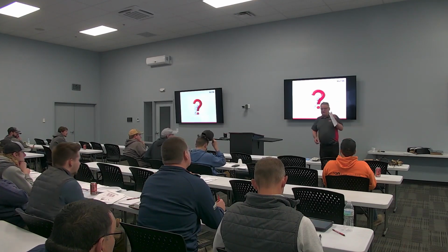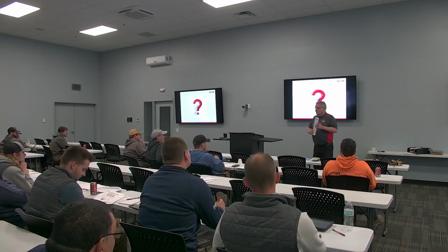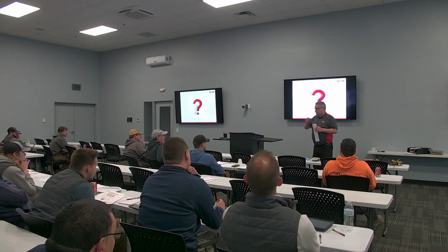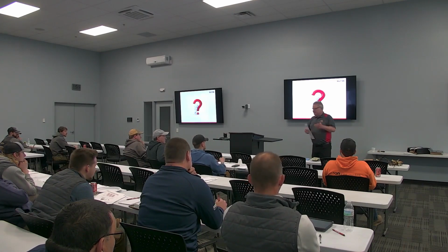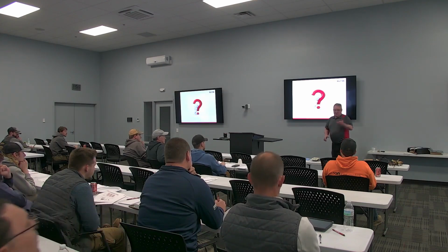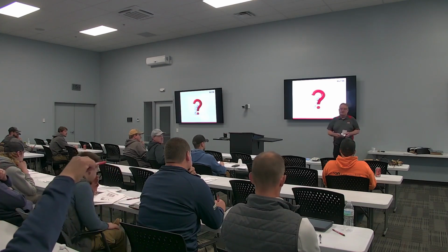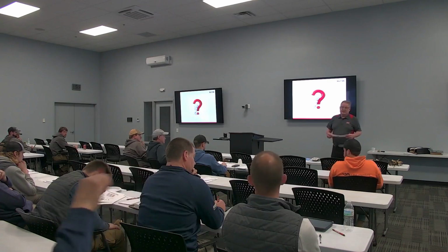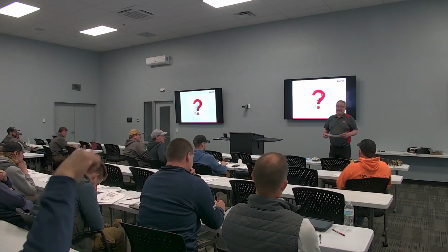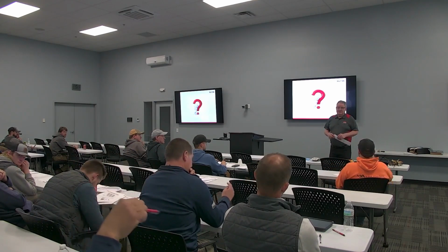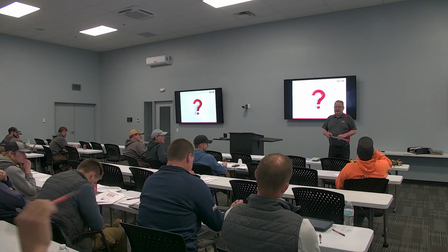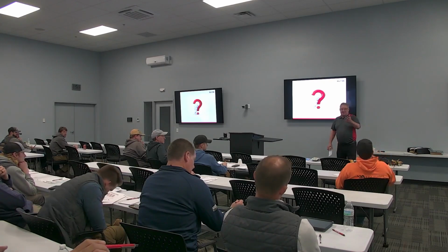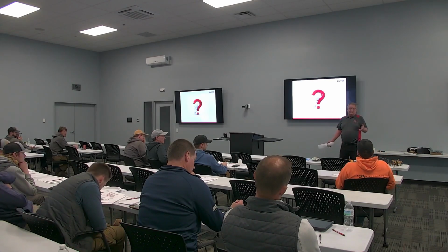Okay, and you'll probably see when you get into PT charts, some of them will have the two listed again because it does have that 2 degree glide. All right, but that's a good point. Yeah, but in the 410A, every unit has a subcooling tag. Yes. Okay, and the 454, they're gonna be something like that? Yeah, they'll be very similar. They're really close. The refrigerants are really close.